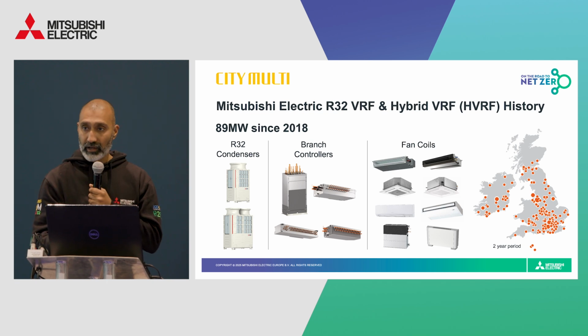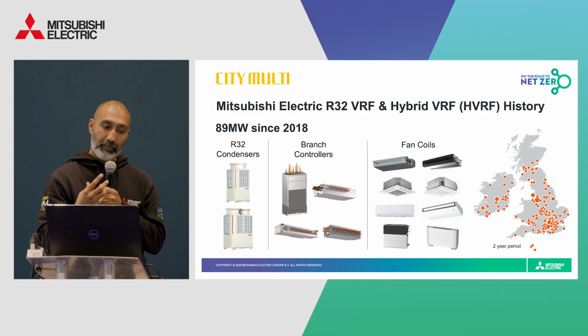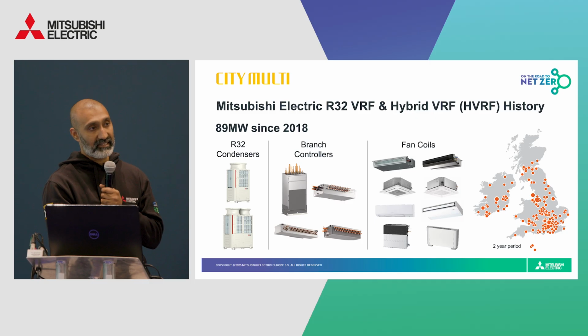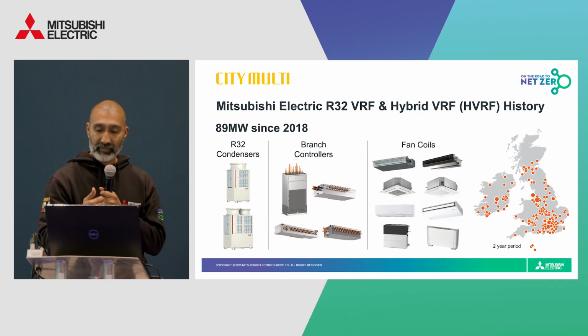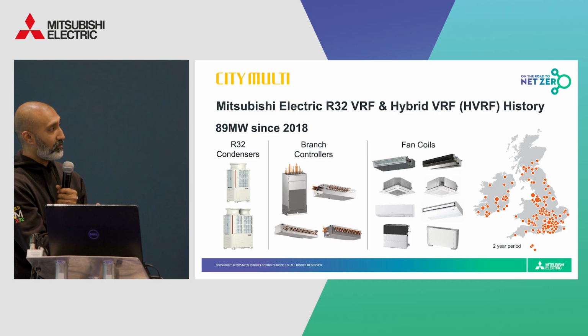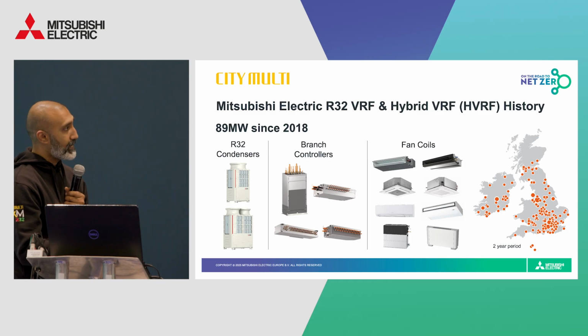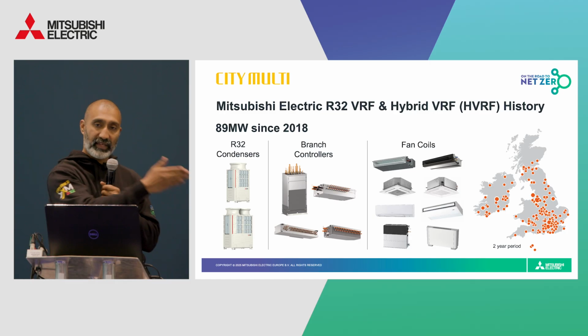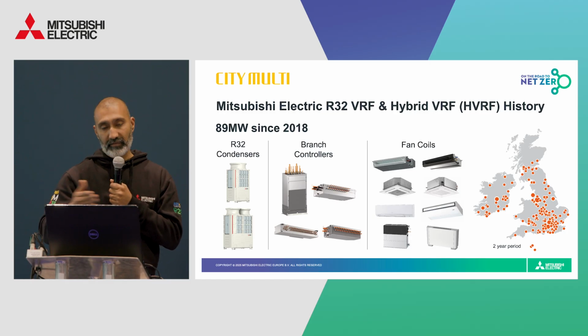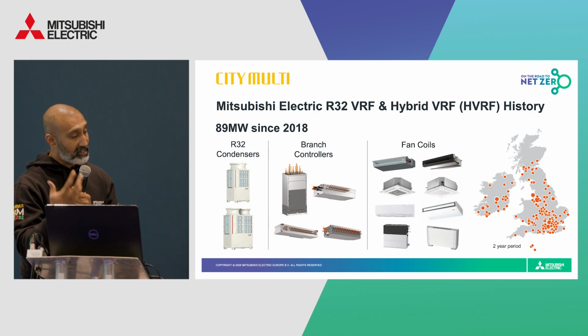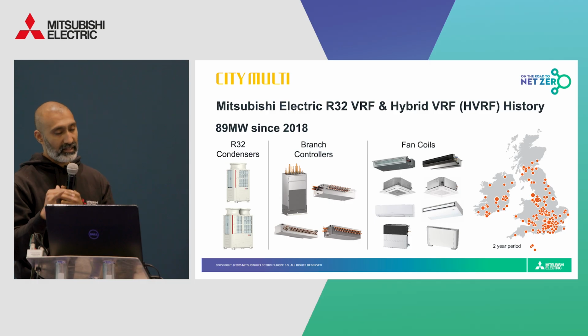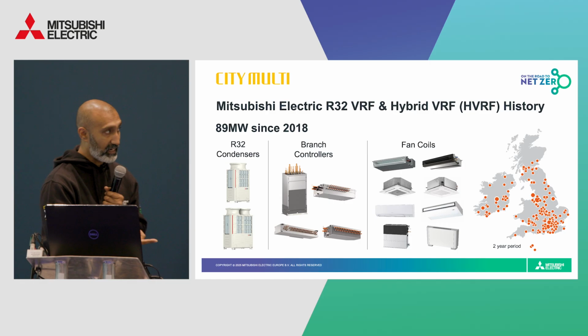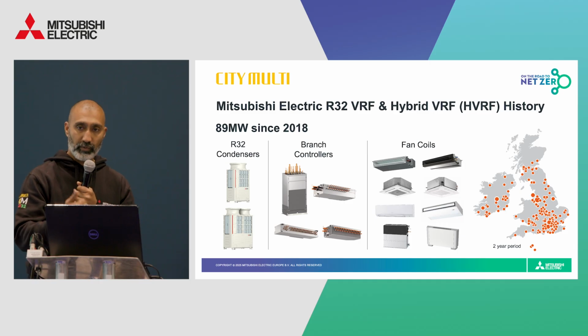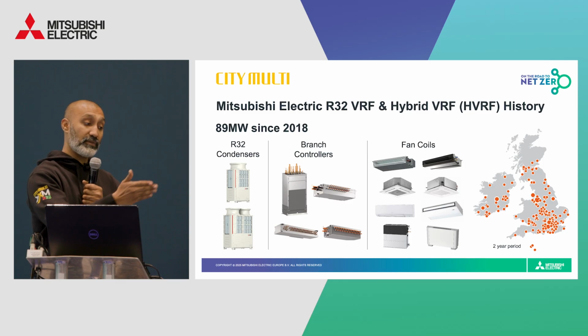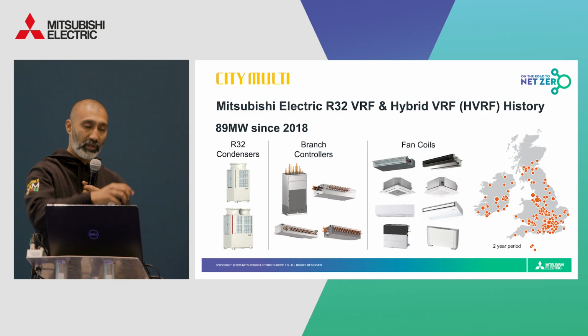So HVRF, or hybrid VRF, delivers simultaneous heating and cooling, but it uses water instead of refrigerant in the occupied space, which is great because it reduces risk to occupants and removes the need for leak detection, saving installation time and costs. Now, at the heart of the HVRF is the hybrid branch controller box, or the HBC. This is connected via traditional refrigerant piping to the outdoor unit, but from the HBC box to the indoor units, you have water piping. Even so, it's still able to deliver mild air-off temperatures and really good stability of temperatures all year round. And additionally, by using R32 refrigerant, we're able to use a refrigerant with a significantly lower GWP, and because the refrigerant is only between the outdoor unit and the HBC box, we have a lower overall system volume.